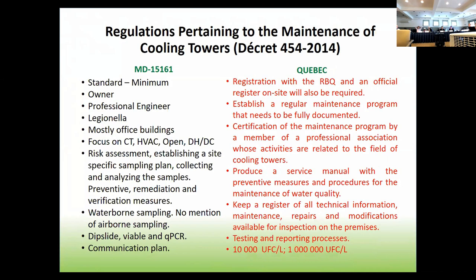I tried to put a few things together. One interesting thing is that if you're an owner of a cooling tower, it's required to be registered with the building department, basically, and there has to be a regular maintenance program established, with testing results sent to the building regulatory body. They use thresholds of 10,000 and a million CFU. Above a million, you literally have to notify the health department immediately, and then they shut everything down and you retest everything. Under 10,000 CFU, there's nothing - you don't have to do anything. In between the two, you have to do some cleaning and make sure everything is tested again.